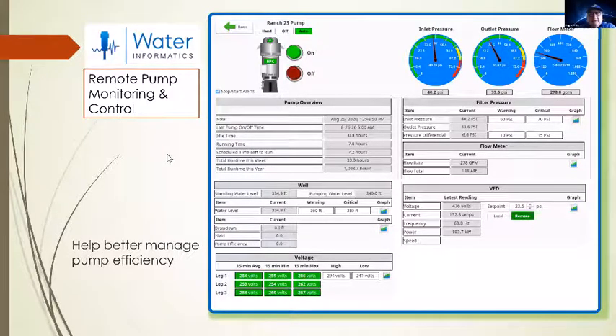What's come about from that is their automation system also measures voltage on lines A, B, and C, and checks that, because in some rural areas, when solar systems come on and tie into a rural location, it can drive the line voltage up on line A and line B well over the capacity requirements of the electric motor manufacturers, and then you get motor failure.